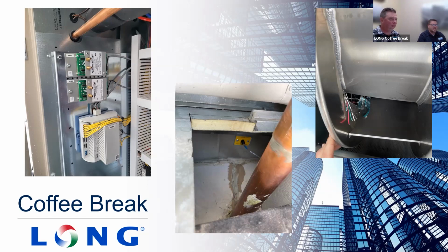So in this circumstance, it creates a commissioning log event where the commissioning agent will say this thing's not performing the way it's supposed to. And this is something that we tend to find, that these are not located in the right spot. The other picture here to the right is, in this particular circumstance, the temperature controls contractor ran a control wire through the fan. And somebody, before we arrived on site to perform the startup, had energized the unit to get the fan running in a temporary capacity and didn't verify that prior to doing it. And a control wire was in the fan when it started. So of course we had to repair that, which created a delay. And it caused some damage to the automation system, which they had to wait on parts and repair, which also added to delay times for turnover for the owner.